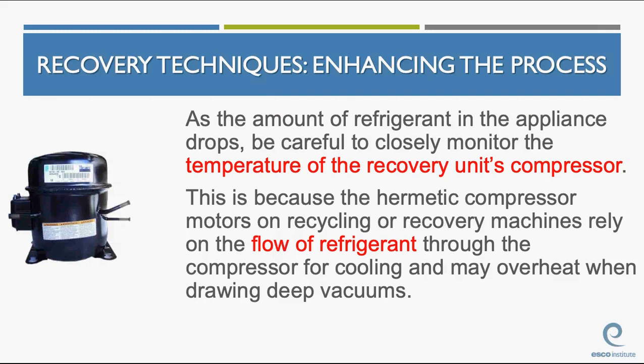As the amount of refrigerant in the appliance drops, you have to be careful to closely monitor the temperature of the recovery unit's compressor. Remember, anytime we have a compressor, the flow of refrigerant through the compressor is what cools it. So if you have a 100-degree day and you're outside running a recovery unit for a couple hours, as that system starts pulling into a slight vacuum, your recovery compressor is not getting a ton of refrigerant moving through it. It may start to overheat. You might have to let it cool down for a little bit and then turn it on again. The flow of refrigerant through these compressors is what cools them.